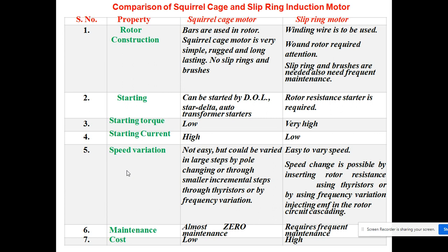or injecting EMF in the rotor circuit, cascading. Maintenance: if we are talking about maintenance, the squirrel cage motor requires almost zero maintenance, but the slip ring motor requires frequent maintenance. And if we are talking about the cost, we can see the squirrel cage motor is more cost effective than the slip ring motor.